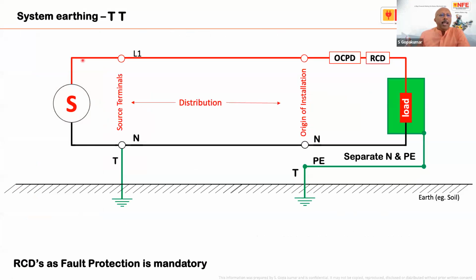Yeah. You see, S is a source. It's a source, maybe DG or transformer or whatever. You have the L1, meaning the current phase conductor, going through an OCPD, MCB, and RCD. So basically, it goes to the load. The neutral returns back to the neutral point. The neutral of the transformer is connected to one earth electrode in soil.